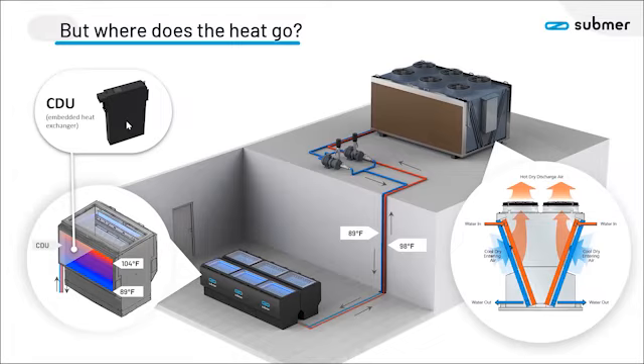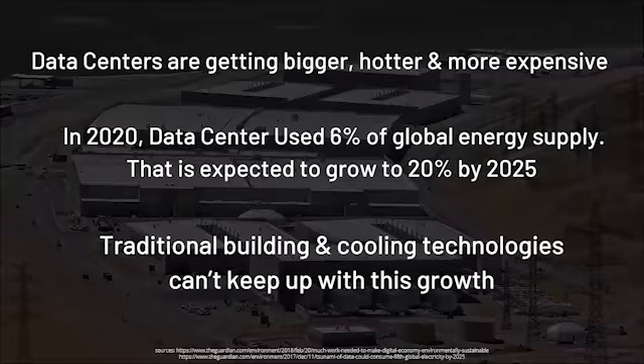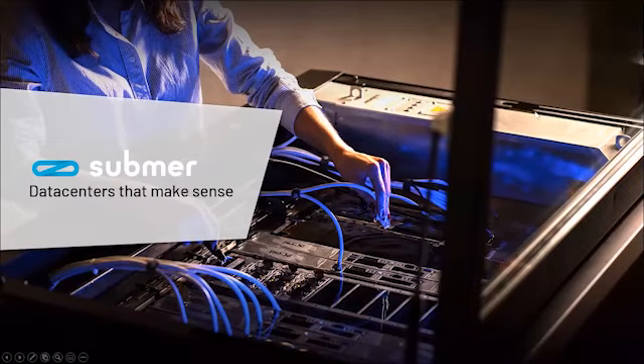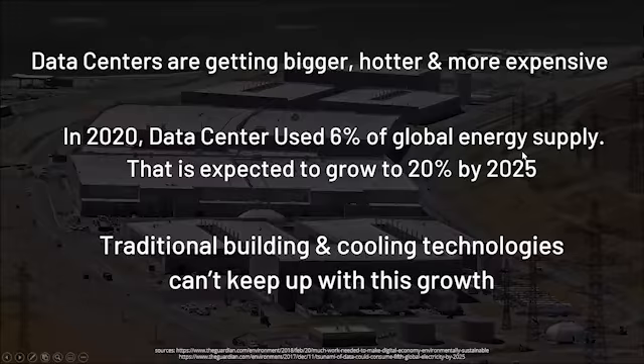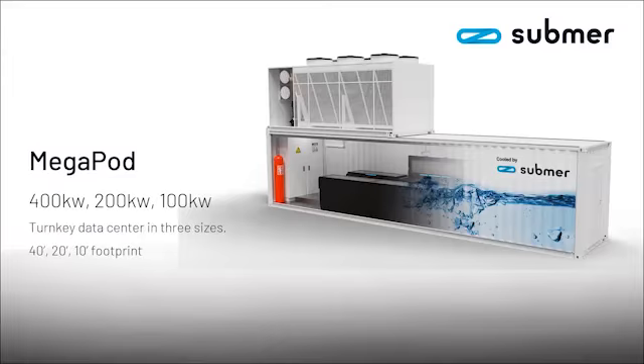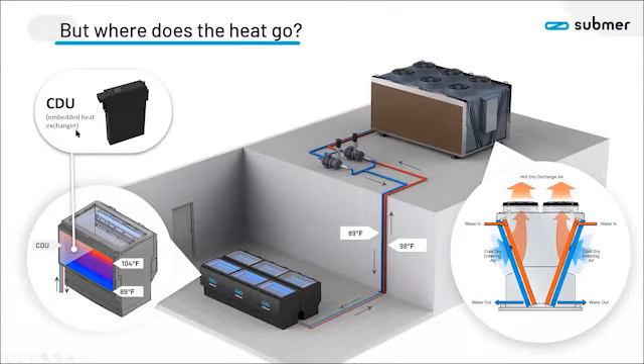That's that silver unit you saw on the very first slide. Let me jump back to it real quick. That's this unit right here, the cooling distribution unit. Inside is my heat exchanger, my pumps, all the intelligence for the system. There's one of these at each end typically, and that's where I'm doing my heat exchange. So our fluid stays inside the tank locally the whole time.